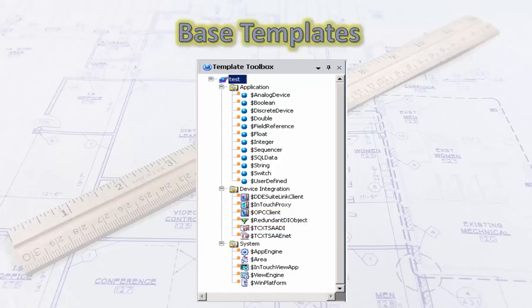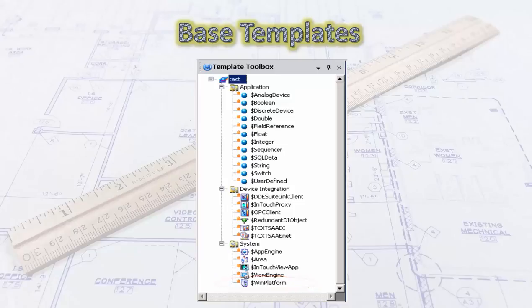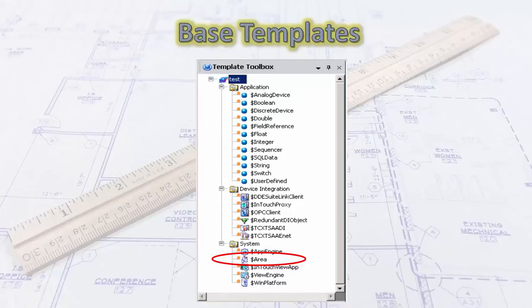The system templates include the WinPlatform template. Everything in the galaxy has to be hosted on a platform. The very first platform you create is going to be your Galaxy Repository platform. Other target computers will need platforms to run engines and areas. The AppEngine template is where engine objects are created. Area objects run on the engine — area objects determine alarm flow hierarchy, so you actually have to put an area on an engine and an engine on a platform.